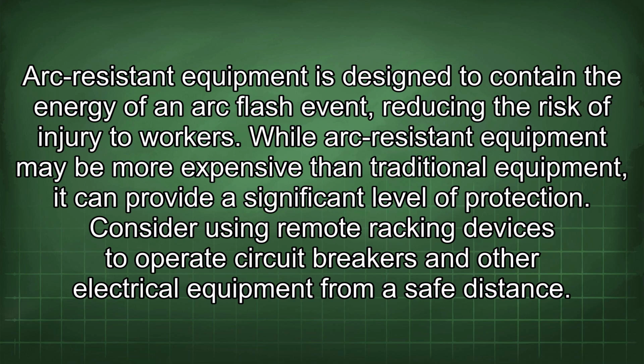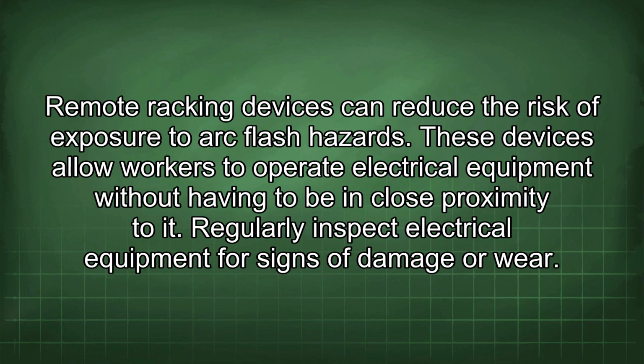Invest in arc-resistant equipment whenever possible. Arc-resistant equipment is designed to contain the energy of an arc flash event, reducing the risk of injury to workers. While arc-resistant equipment may be more expensive than traditional equipment, it can provide a significant level of protection. Consider using remote racking devices to operate circuit breakers and other electrical equipment from a safe distance. Remote racking devices can reduce the risk of exposure to arc flash hazards. These devices allow workers to operate electrical equipment without having to be in close proximity to it.